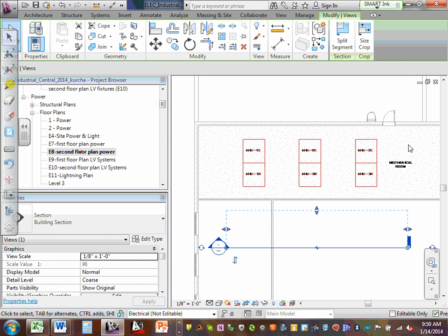In other words, you could have a fire on the opposite side of the building, but the air handler that serves this room, and we could be sitting here talking and having class and having a good time, and all of a sudden we got smoke coming out of the diffuser. What the hell's going on? So you want to shut her down, so we can eliminate that potential.